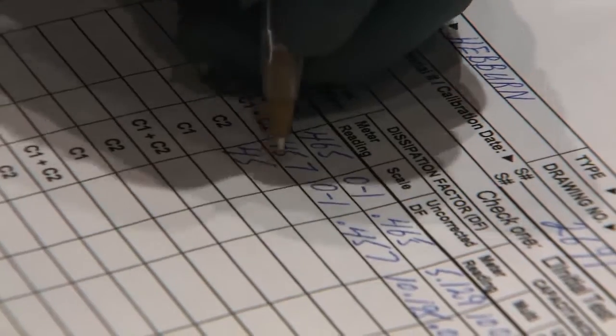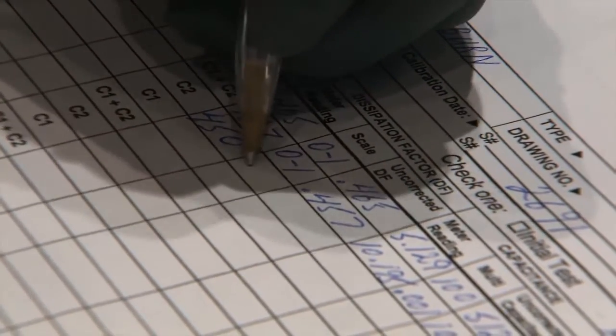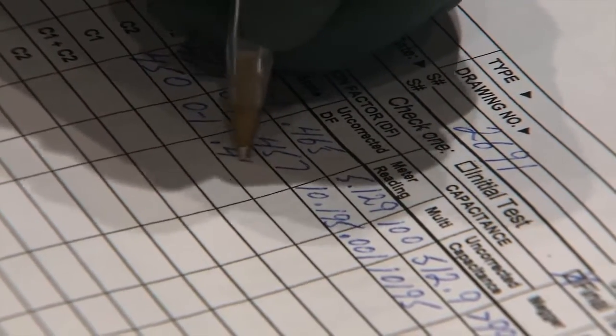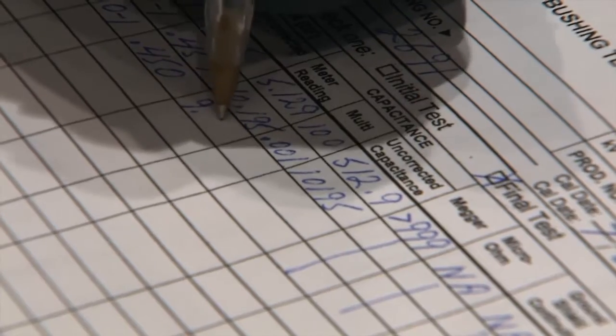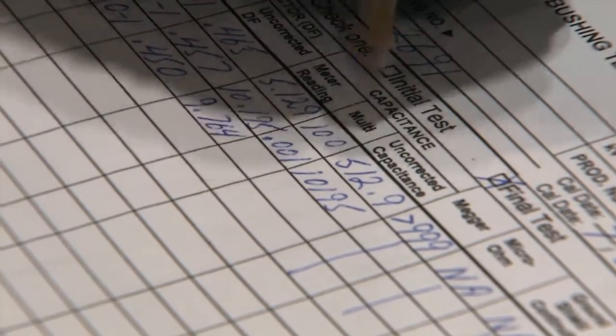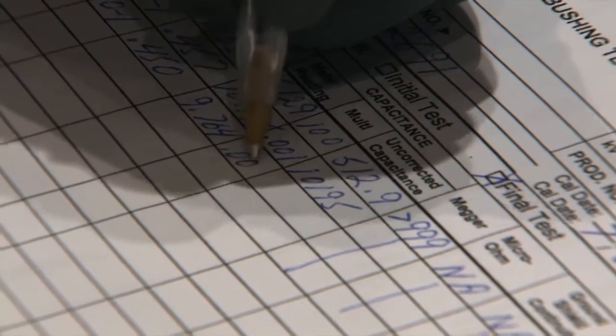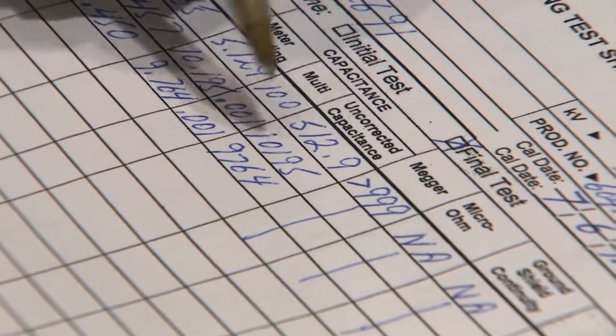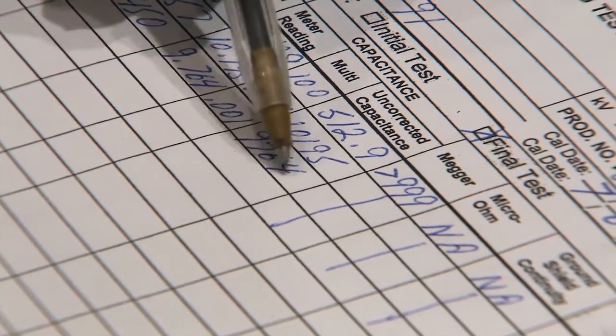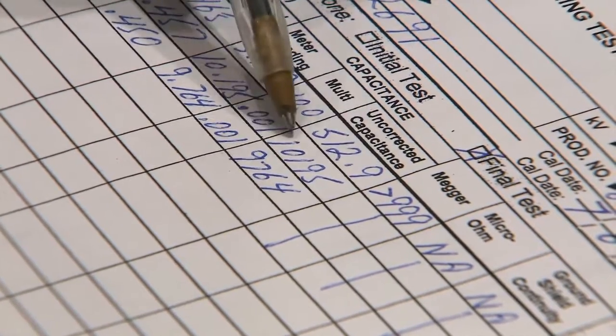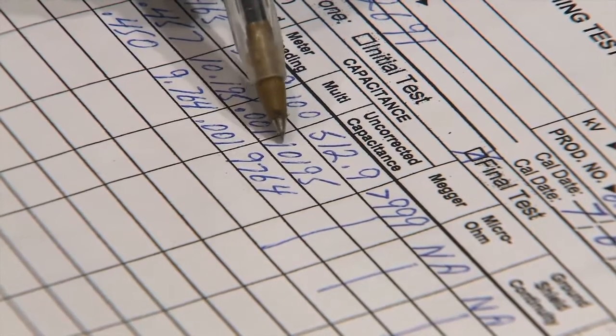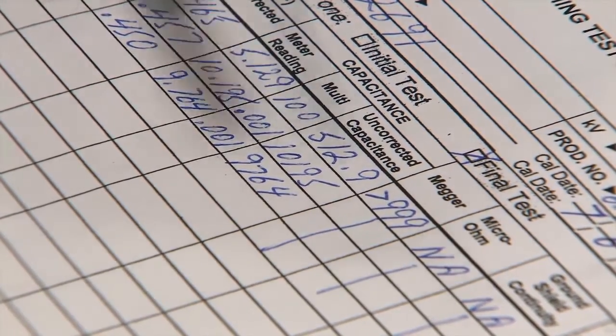The dissipation factor was 450, and it was at a scale of 0 to 1, which gives it an uncorrected DF of 0.450. The meter reading was 9.764 picofarads with a multiplier of 0.001, which gives it 9,764. So when you add 9,764 to 512, you come very, very close to your C1 plus C2 test. So it's just a confirmation.